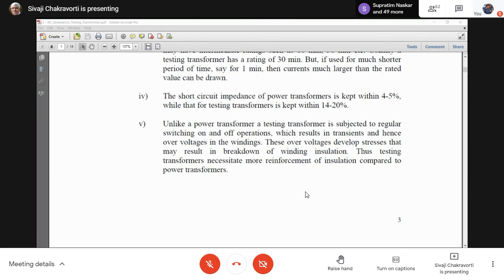Whereas a testing transformer will be almost every day switched on and off. And therefore, switching transients on the internal insulation of the transformer is much higher for the testing transformers. And therefore, when we design the insulation of the testing transformer, we design it differently from the power transformers. So that's another difference.